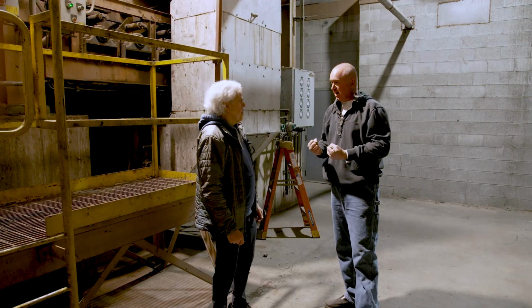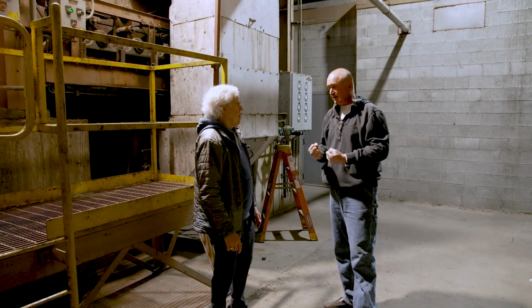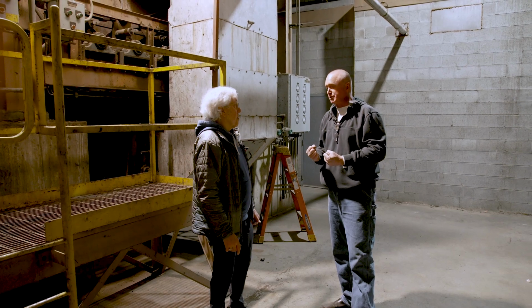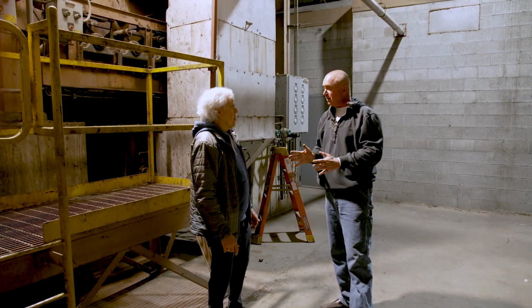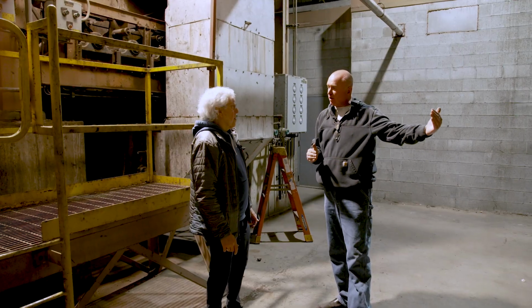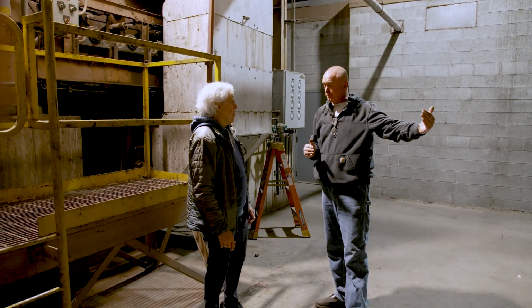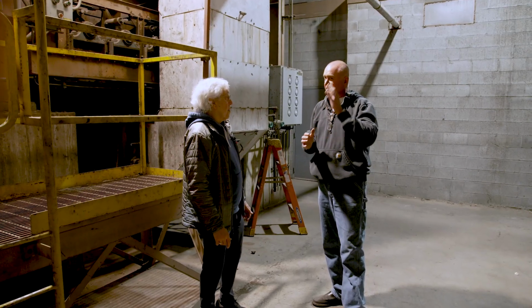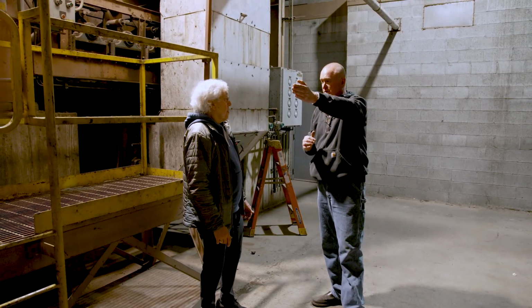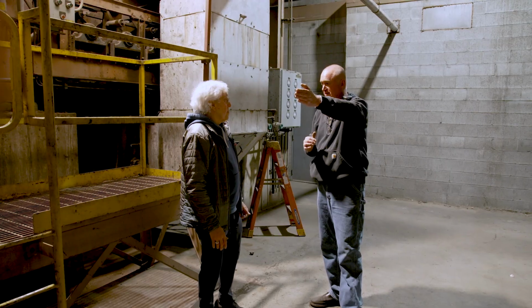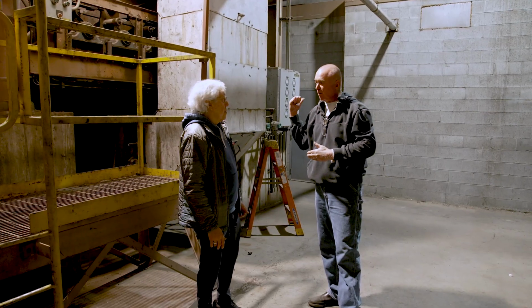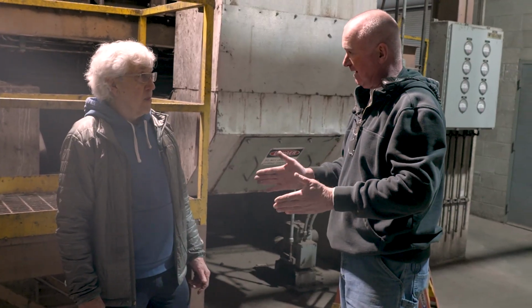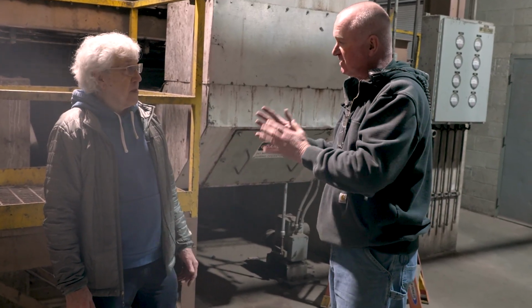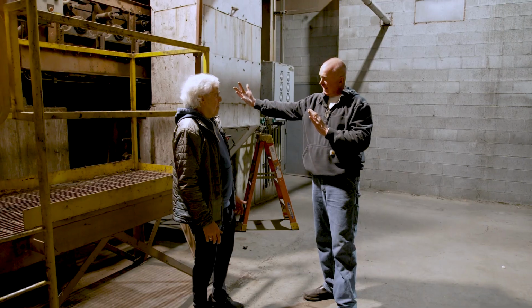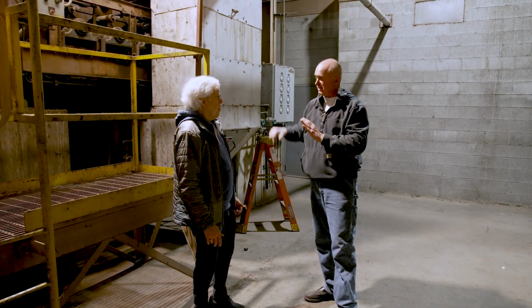That steam is 850 degrees Fahrenheit at 820 pounds per square inch. From there, we send the majority of that to the turbine generator, but we also support the steam demands of plant 4, which is process steam, that's 300 pound steam, and the steam demands of plant 1 and 2, which is 65 pound steam. So we're supporting their processes with the extra steam generated through this process. Let's go look at the next step.